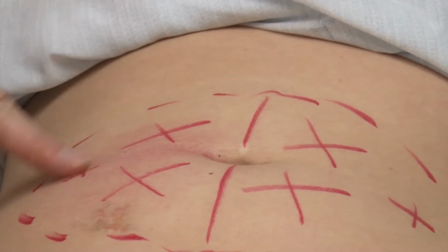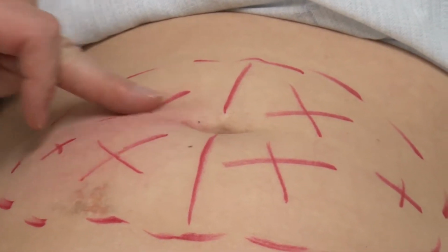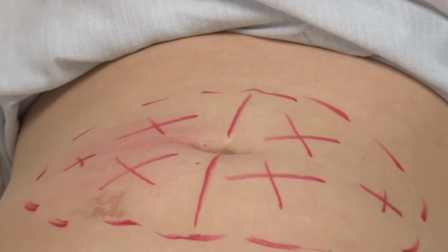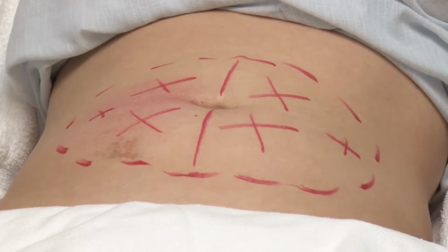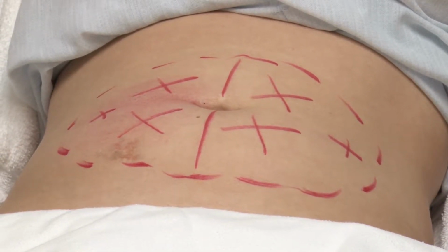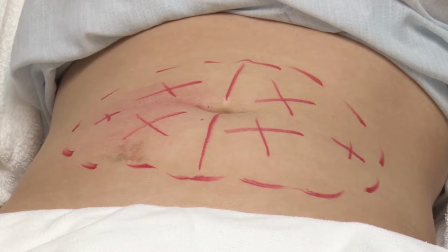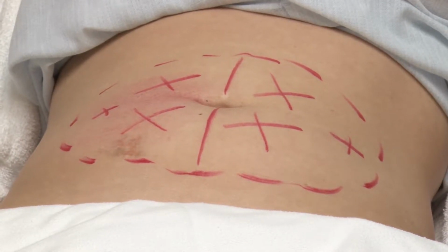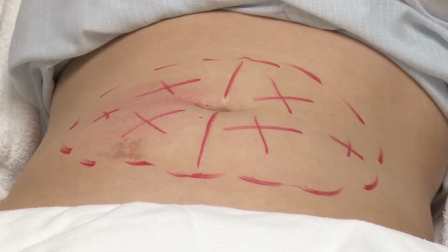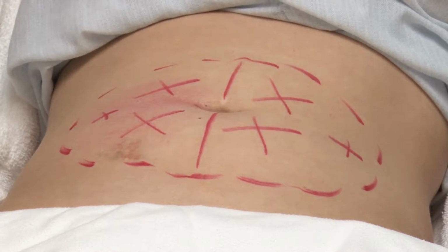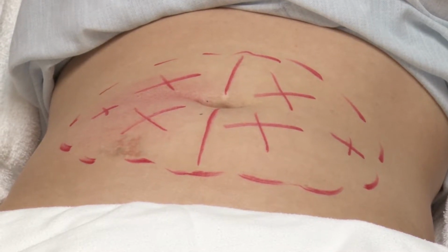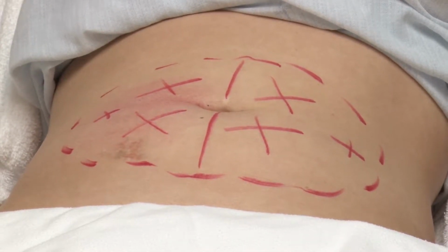Now take a look here. We've got a little erythema, which is from the suction and the heating. Now we're going to take it up to therapeutic endpoint. Therapeutic endpoint is 42, 43, or 44 degrees epidermal temperature, which is 1 degree higher, usually up to 2.5 centimeters down. Whatever the patient can tolerate. Most can tolerate 42, some 43, and some 44 degrees. You want to get it at least to 42 degrees.